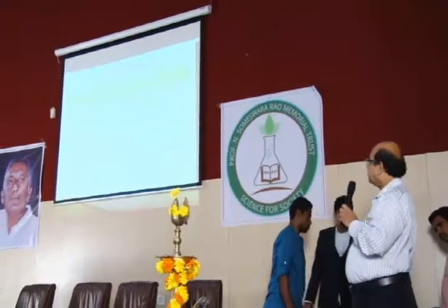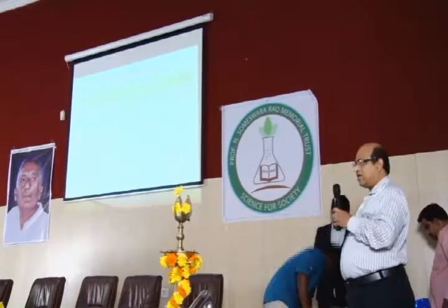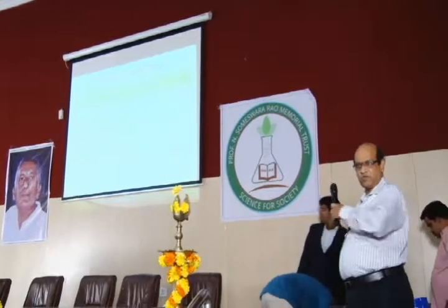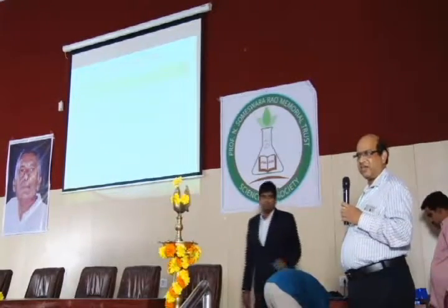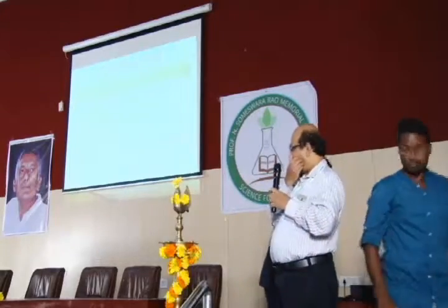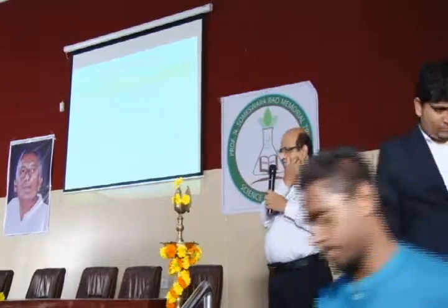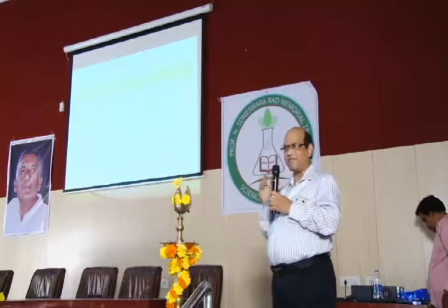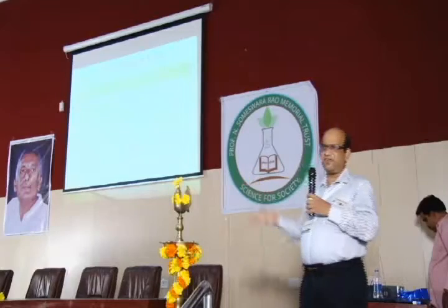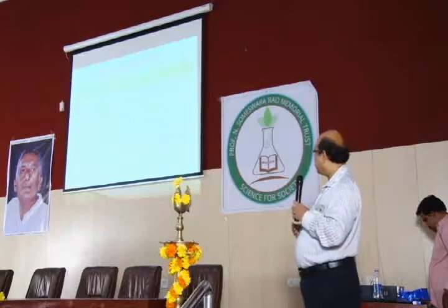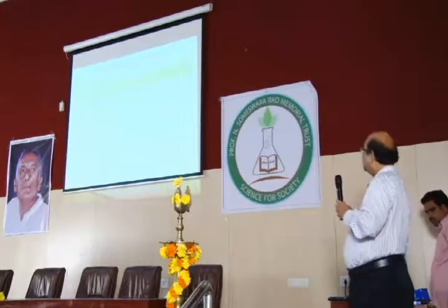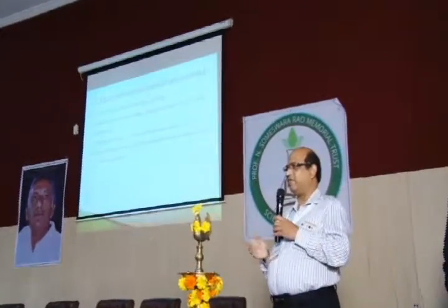Next, oil and grease traps also. Nowadays the latest oil and grease traps are there, but still there are some problems with the conventional ones. The latest are API separator, TPI separator, and dissolved air flotation. Wherever we suggest now, I think we have to suggest only DAF. But when ETPs are already there, we have to see all these problems. Sometimes oil will go through, some soil is there, and sometimes wash water will come.